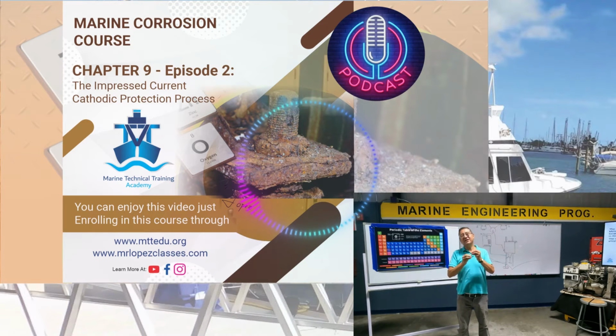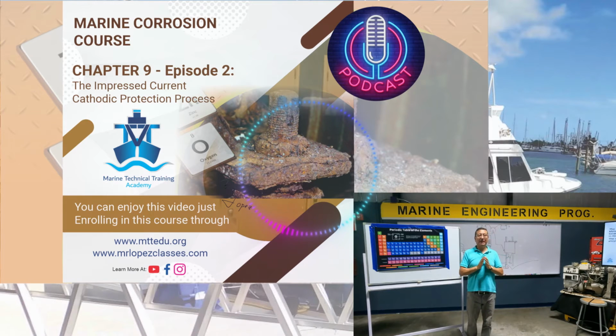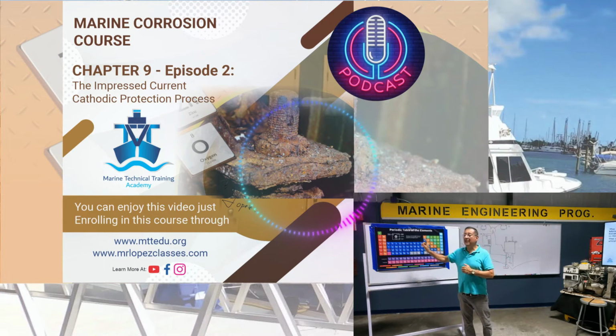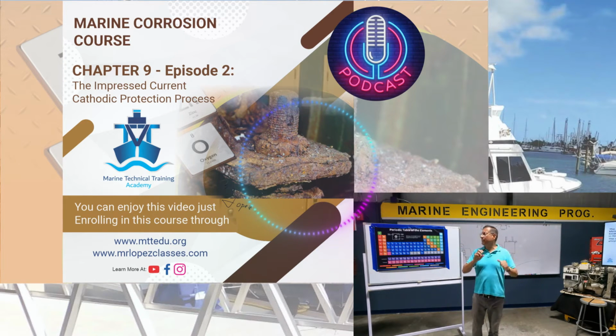Impressed current cathodic protection works by delivering a controlled amount of DC current. Look, this is the DC, the source of DC power. The negative is connected directly to the structure. And the positive cable is connected here to the anode.